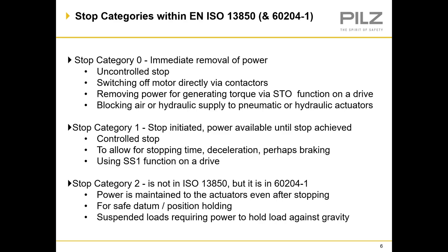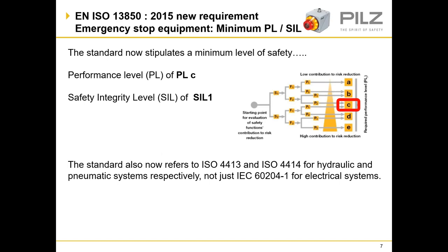Moving on to the new requirement relating to the functional safety standards. This new inclusion into EN ISO 13850 refers to the minimum performance level and safety integrity level requirements for an emergency stop: a performance level of C, or a safety integrity level of 1. The risk graph from Annex 1 of EN 13849 part 1 is referenced because of this introduction of a minimum safety level for e-stops — performance level C using 13849, or SIL 1 using 62061. Standard 13849 is most commonly used by manufacturers of machinery rather than 62061, which is mainly for the process industry.